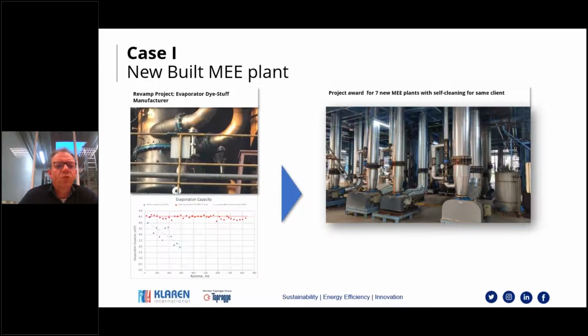And this customer was really looking for a solution for that problem. So we installed, as said, the self-cleaning evaporator. We retrofitted their installation. And after the retrofit, you see the performance with the red triangles. And you see that in the period in this graph of 800 hours, the evaporation capacity fluctuated a bit, but on average was completely and perfectly constant. So this was also really to the comfort of the client, who then asked us to also equip new MEE plants with the self-cleaning technology.